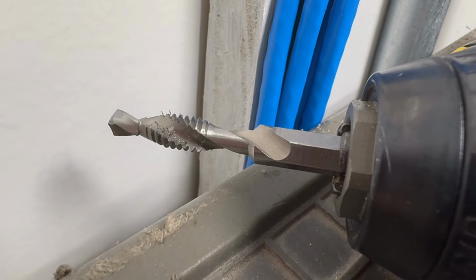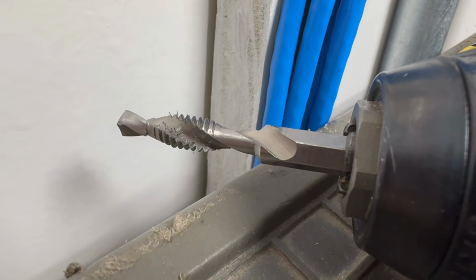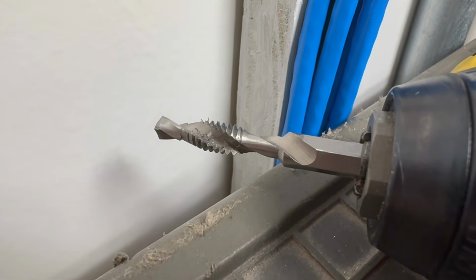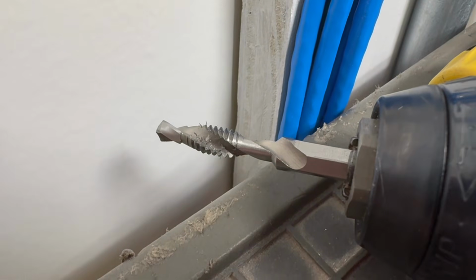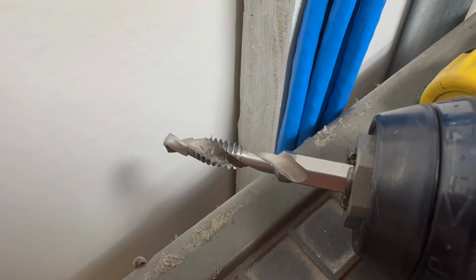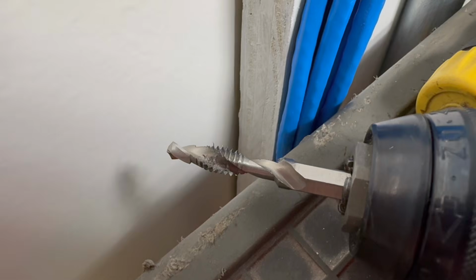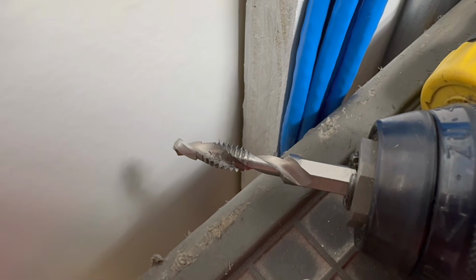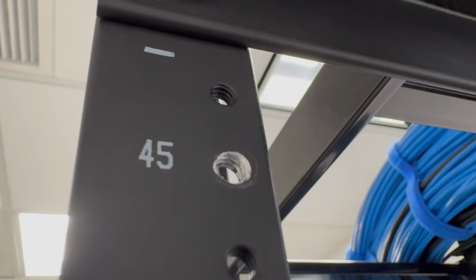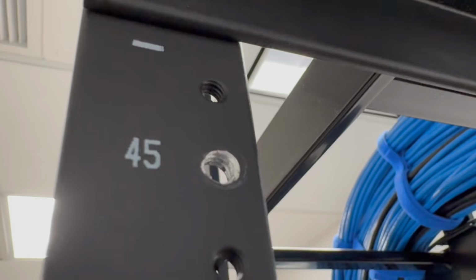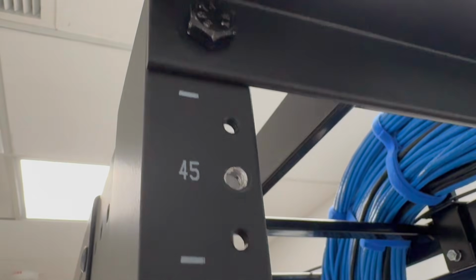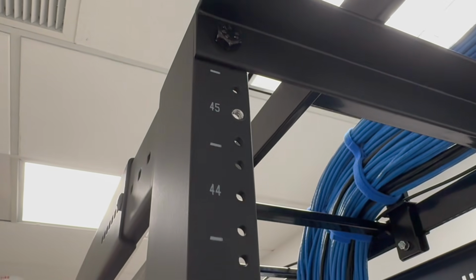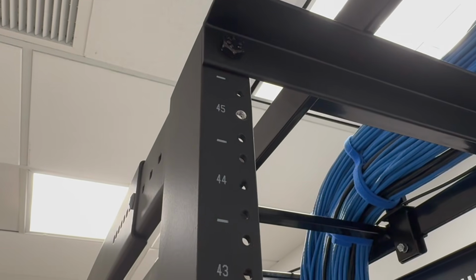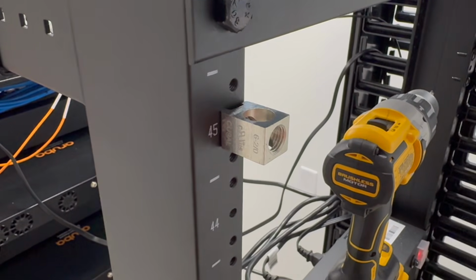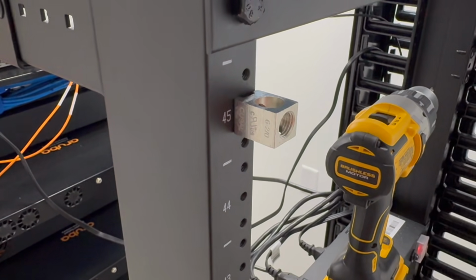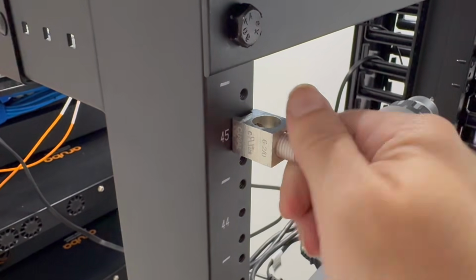I'm going to use this tap kit to put a threaded bolt right through one of the normal screw holes on my rack. That will wear away the paint, which is also pretty important—the paint has higher resistance than the metal underneath, and I want to give electricity the easiest path it can get to ground. It's good practice wherever two painted pieces touch each other to take a wire brush and wear away the paint so the metal contacts directly.